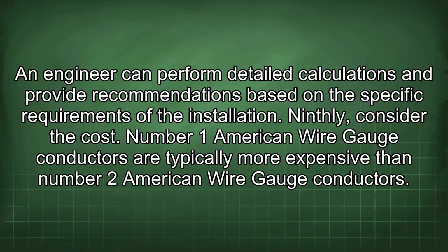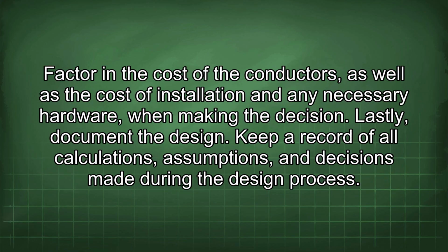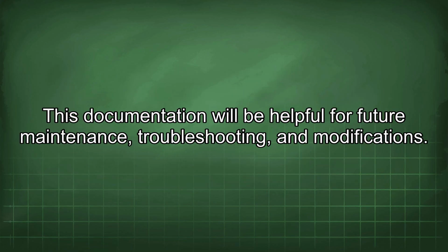Ninthly, consider the cost. Number 1 American wire gauge conductors are typically more expensive than number 2 American wire gauge conductors. Factor in the cost of the conductors, as well as the cost of installation and any necessary hardware, when making the decision. Lastly, document the design. Keep a record of all calculations, assumptions, and decisions made during the design process. This documentation will be helpful for future maintenance, troubleshooting, and modifications.